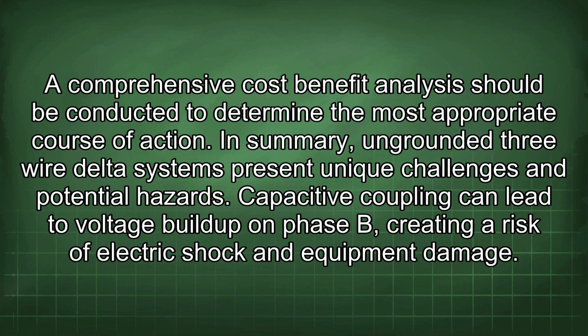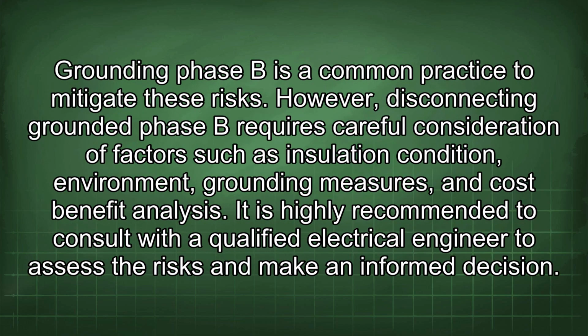In summary, ungrounded three-wire delta systems present unique challenges and potential hazards. Capacitive coupling can lead to voltage buildup on phase B, creating a risk of electric shock and equipment damage. Grounding phase B is a common practice to mitigate these risks. However, disconnecting grounded phase B requires careful consideration of factors such as insulation condition, environment, grounding measures, and cost-benefit analysis. It is highly recommended to consult with a qualified electrical engineer to assess the risks and make an informed decision.